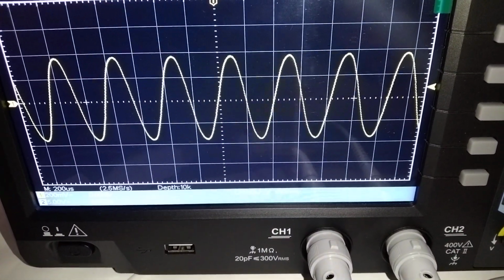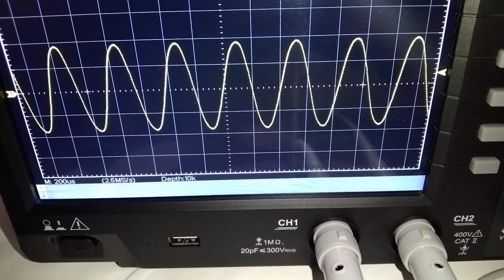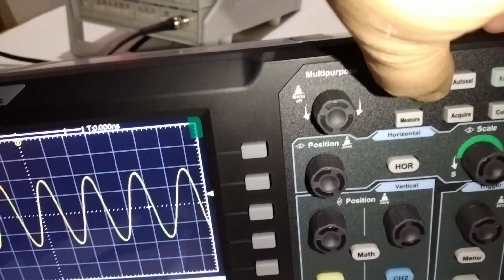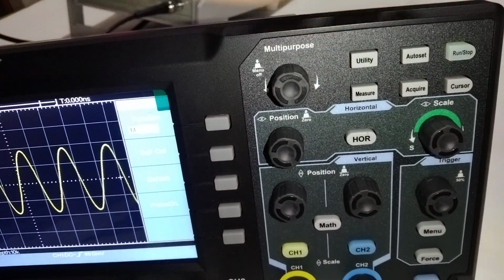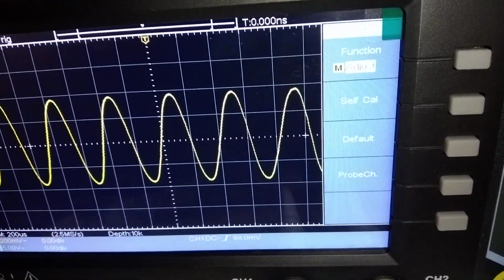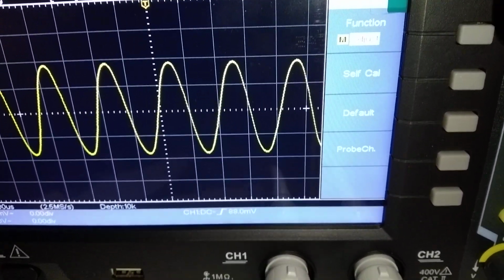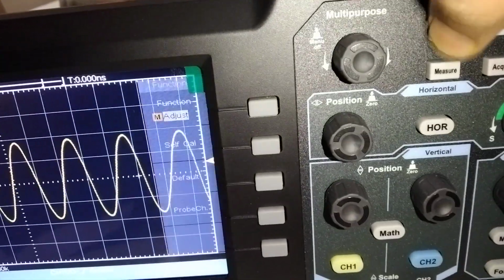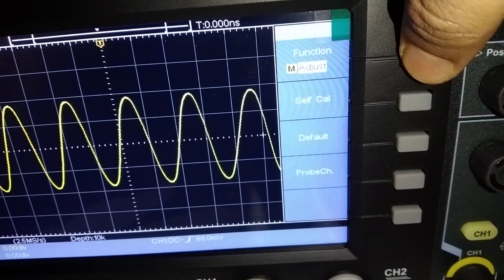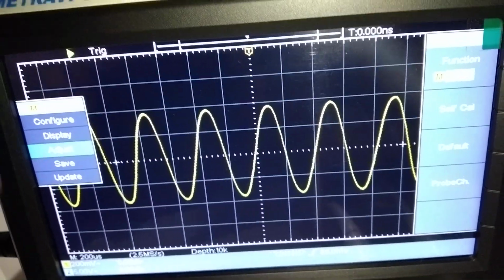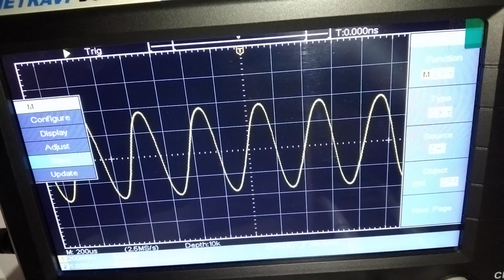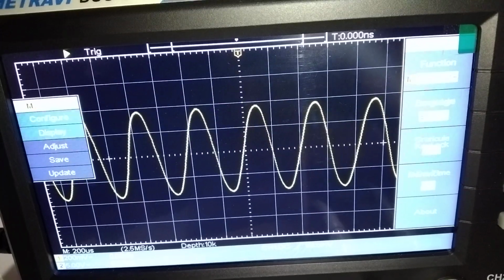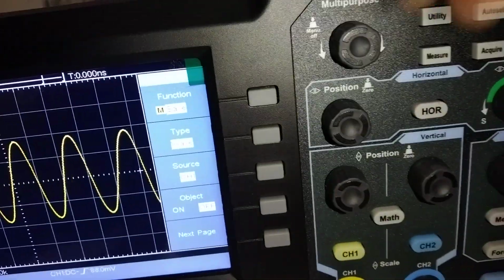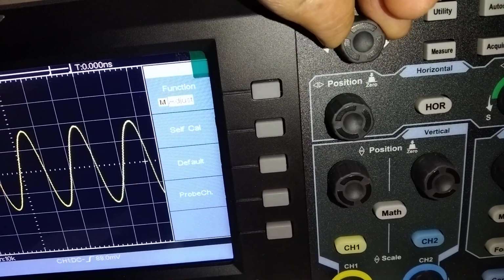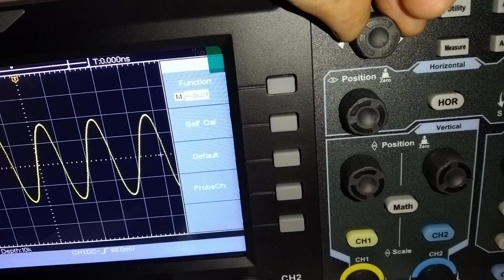Now once it checks and shows you this screen, you first have to push the utility function or utility button. When you press the utility function, you have to select the adjust. See, again I'm pressing the utility button. Here at this side there are many options. You can vary this, or you can also vary from this multi-purpose knob, right? So you have to first select the adjust in the left menu, and select the default in the right menu. So here default must be selected.